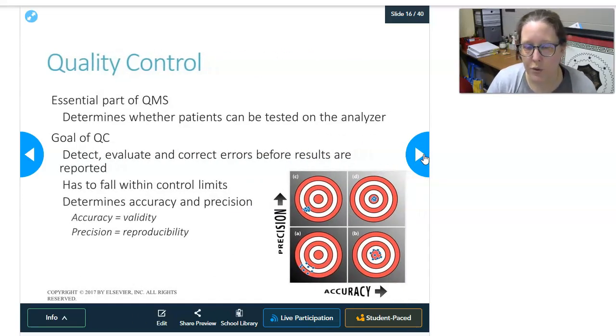So quality control on the analyzers is an essential part of the quality management system, and basically it determines whether patients can be tested on the analyzer. If you are running your quality controls, which you know the target values for, and you're not getting accurate or reliable results, then you have no business turning out patient results, because that means your patient results aren't going to be accurate or reliable. So the goal of quality control on these analyzers is to detect, evaluate, and correct errors before the results are reported. And until you resolve your quality control issues, you cannot report any of those patient tests out.